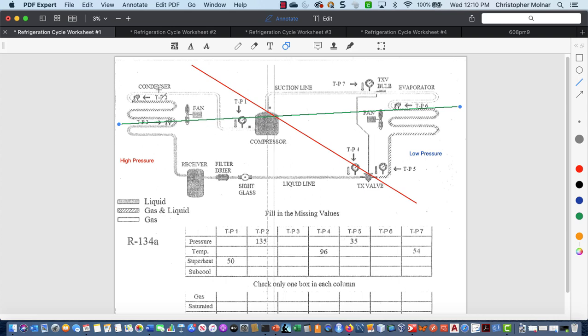We come out of the compressor as a high pressure vapor. We de-superheat, we start to condense, and by the time it comes out of the condenser, it's a liquid. As we come into the evaporator, it's a flash gas, which is actually a low pressure liquid. Then we boil it off, absorb heat, and by the time we're in the last pass of the evaporator, we should be 100% vapor coming back to the compressor.